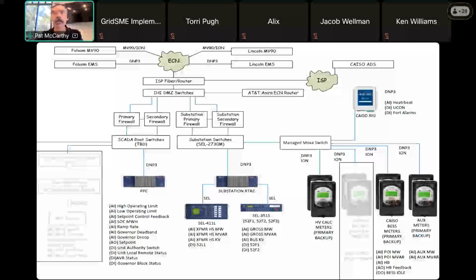So when we're talking about data that's sourced at a relay, you either need a relay test set to be able to push current and voltage into a relay and produce transformer high side megawatts, transformer high side voltage, gross megavars down at that 351S I have on the screen.